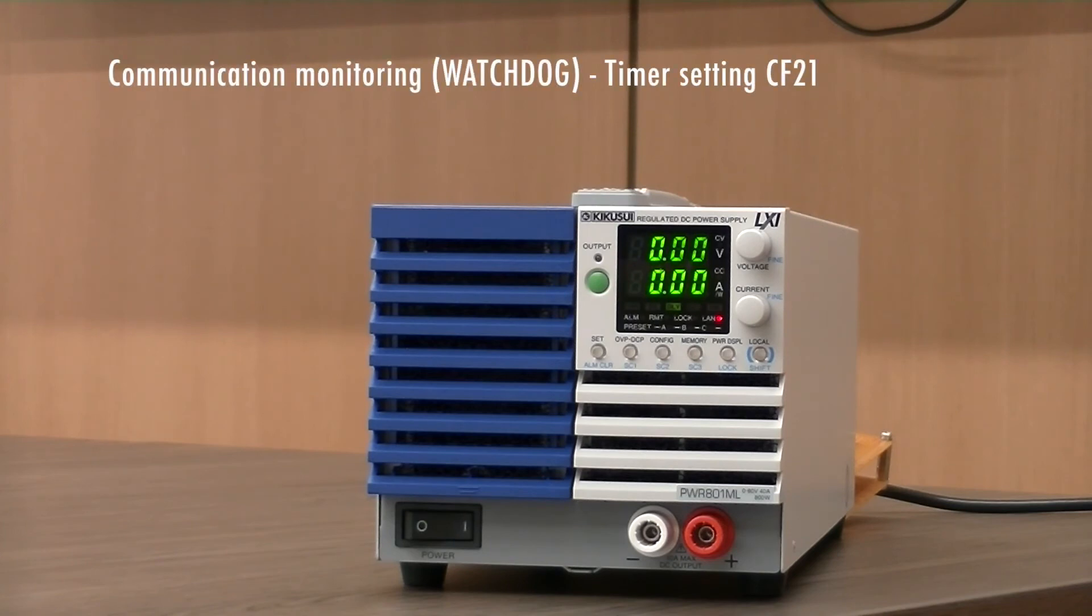One safety feature that we are often asked about is the watchdog protection. The purpose of the watchdog function is essentially to monitor the SCPI command's communication status and judge whether communication has stopped when there is no communication within the time period specified by the communication monitoring timer setting, which can be set via config 21.